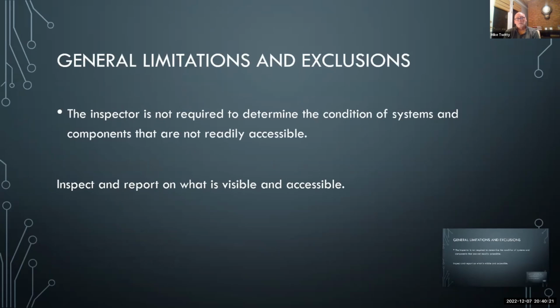Okay, here's another statement from the ASHI standard of practice. The inspector is not required to determine the condition of systems and components that are not readily accessible. A lot of the grounding electrode system in a home is not readily accessible. Unless you're there when it's being installed, you're not going to be able to inspect and confirm everything is as it should be. So that's not a real big deal. I mean, we're generalists as home inspectors. As an electrical inspector, you go a little more in depth, but even then you're limited in what you can see and what you can confirm.